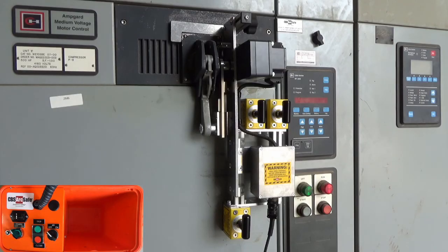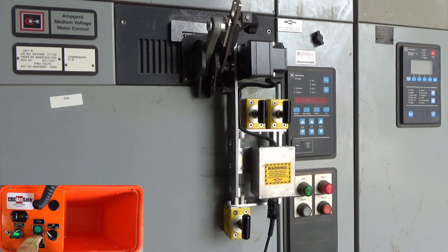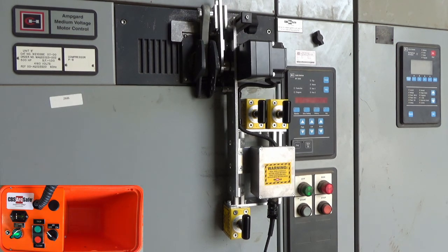To operate the RSO, connect the 4-pin cable from the RSO to the device, and turn on the RSO. Press and hold close to move the handle operator to the closed position. Press and hold trip to move the handle operator to the tripped position.